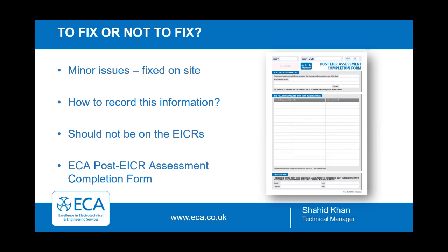To fix or not to fix? This is a common question on the helpline and also in industry. When conducting a periodic and you come across minor faults that you've fixed as you've been going along, should this information be recorded on an EICR? Technically, the correct answer is no. The EICR is simply to comment on the current state of the installation, and if some of the items have been fixed, they no longer are an issue, so shouldn't be commented on.